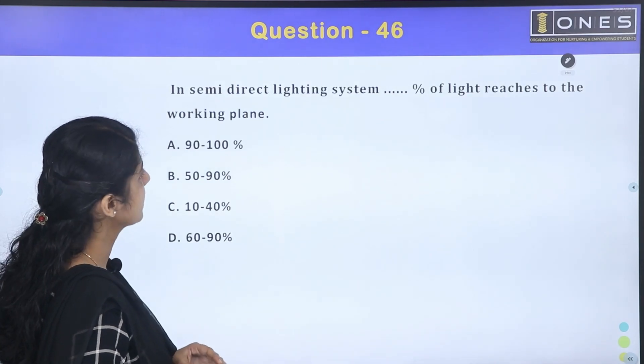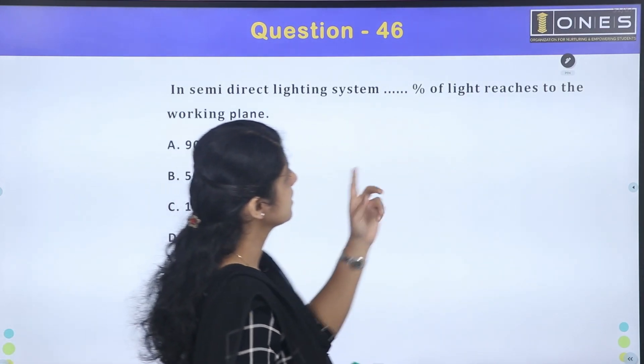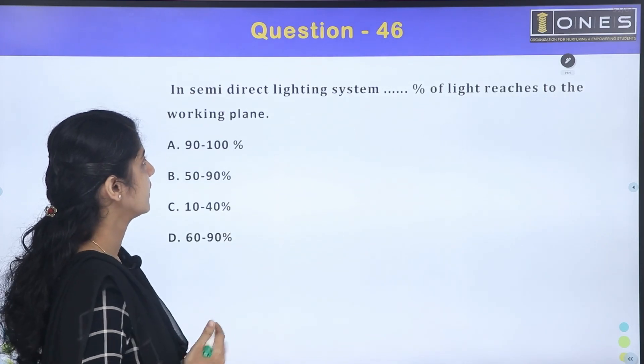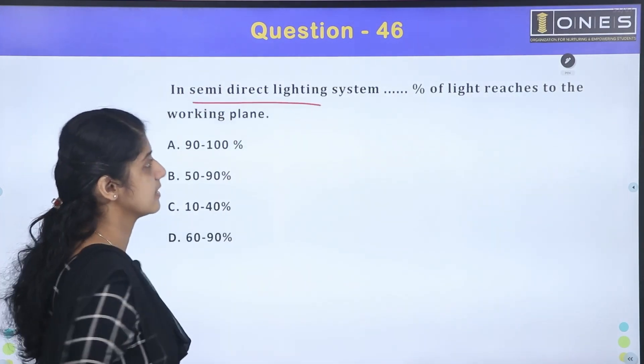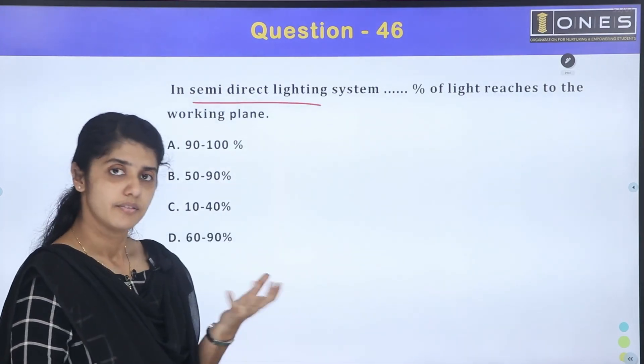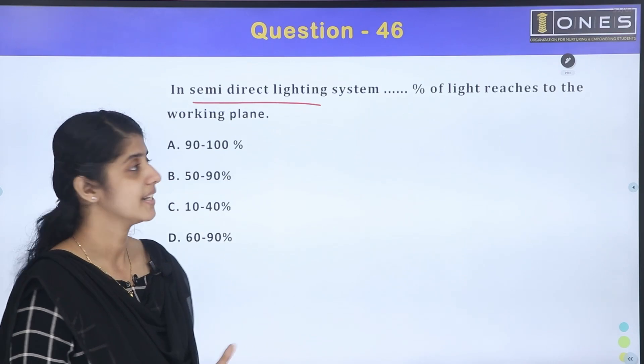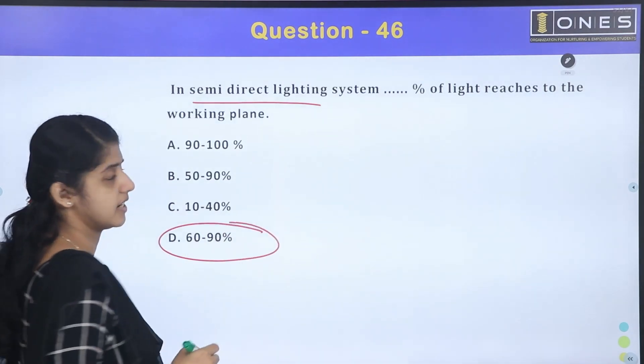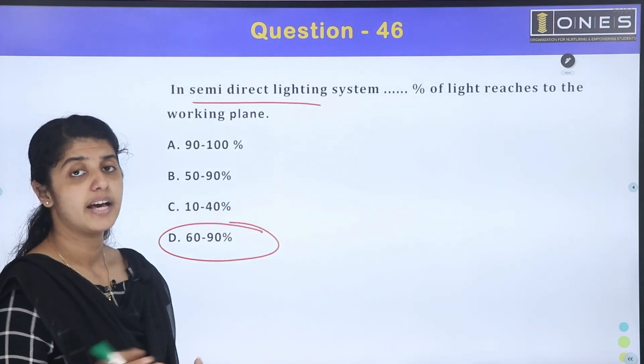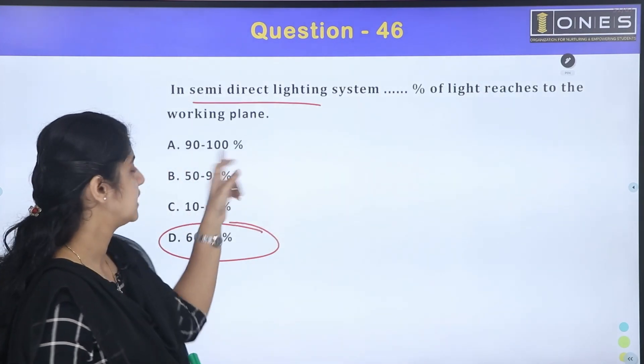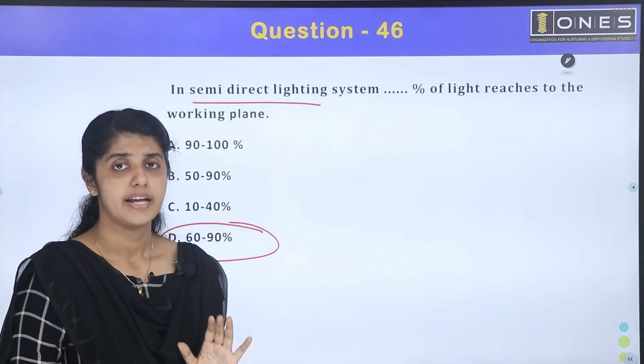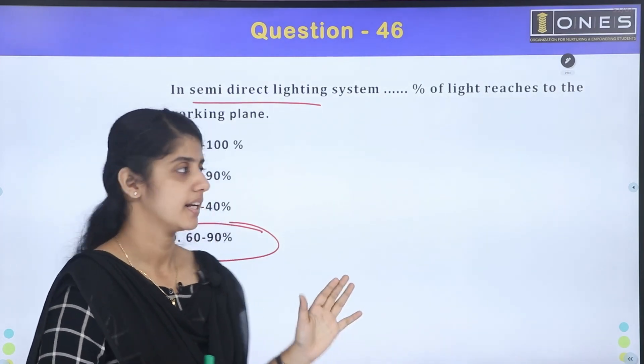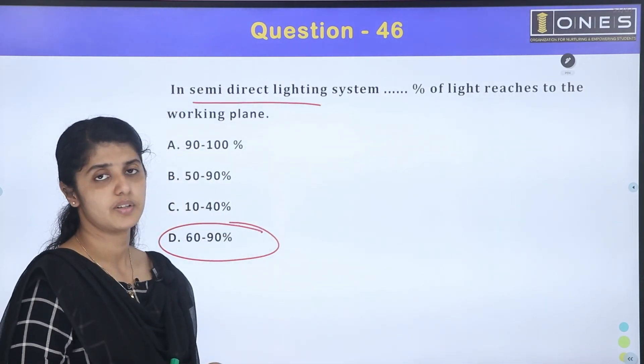In a semi-direct lighting system, a large percentage of light reaches the working plane. The direct lighting system delivers 90 to 100% of light to the working plane, while the semi-direct lighting system delivers 60 to 90% of light to the working plane.